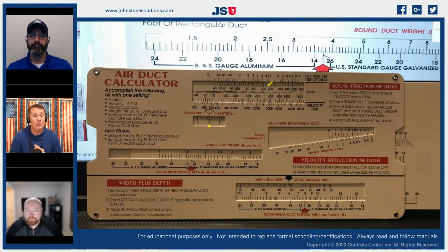So we have to stick to our guides of airflow. We have to keep these systems around 0.5 inches. So we need to design our ductwork at 0.1 inches and lower to be able to maintain these standards. So if you're setting up your ductwork properly, you can get all sorts of airflow. Just make sure that you're setting it up properly, because it can go just the opposite direction. Because you may get engineering specs that say your supply ductwork needs to be designed at a 0.05. I have seen 0.05 engineering specifications before.